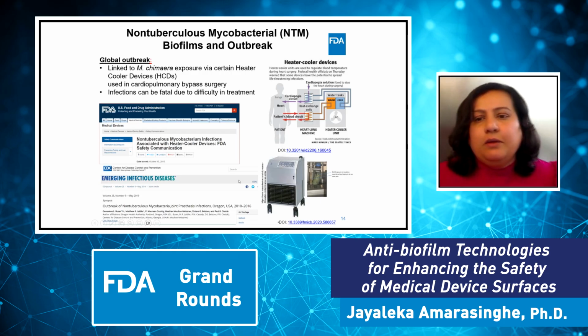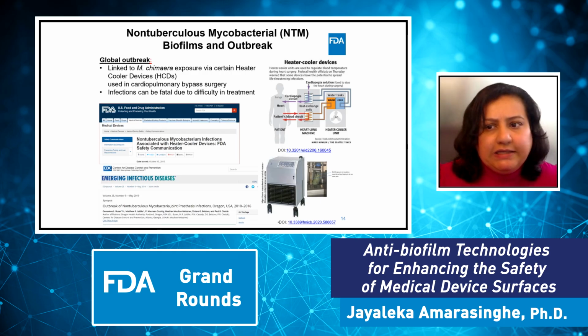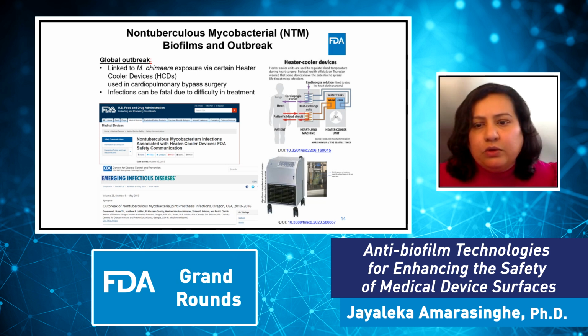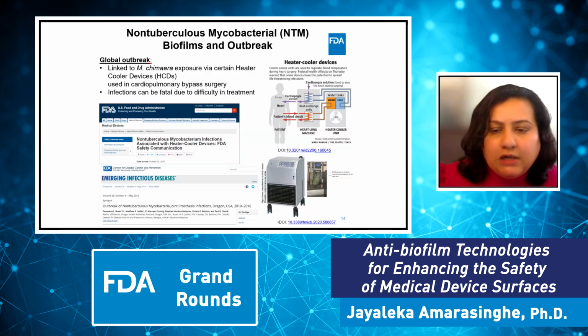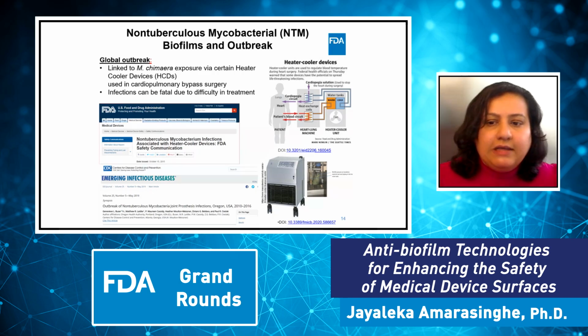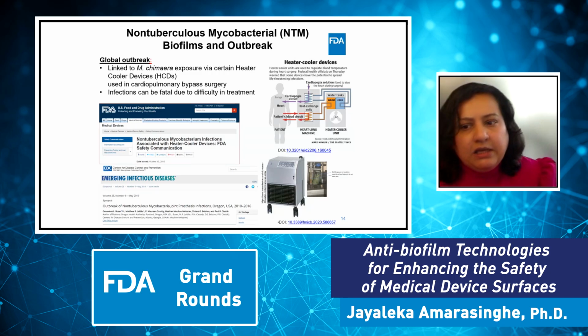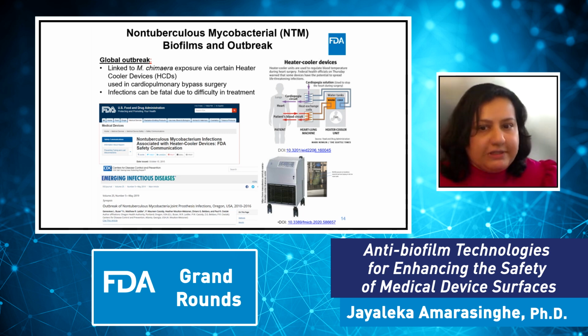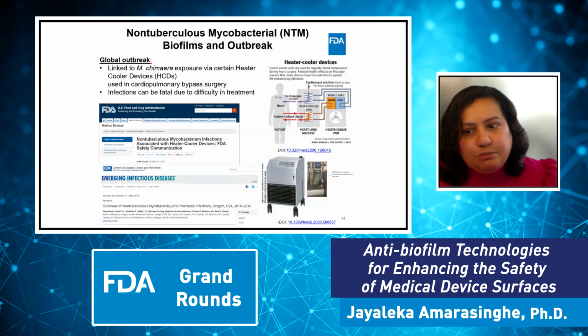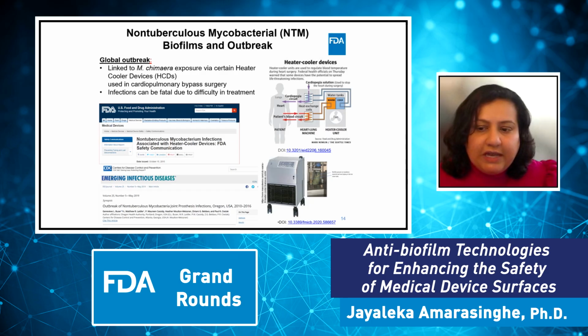So one of the most alarming examples of a biofilm-related NTM infection is the Mycobacterium chimaera outbreak linked to heater-cooler devices that happened recently. These devices are used during open heart surgeries. Although these heater-cooler devices don't come into direct contact with the patients, contaminated internal water tanks colonized during manufacturing allow biofilm-laden water to aerosolize and expose patients during surgery. So the biofilm persisted despite standard cleaning protocols, leading to global exposure, difficult to treat infections, and in some cases, fatal outcomes. So the outbreak triggered FDA safety alerts, device recalls, and also international health warnings.